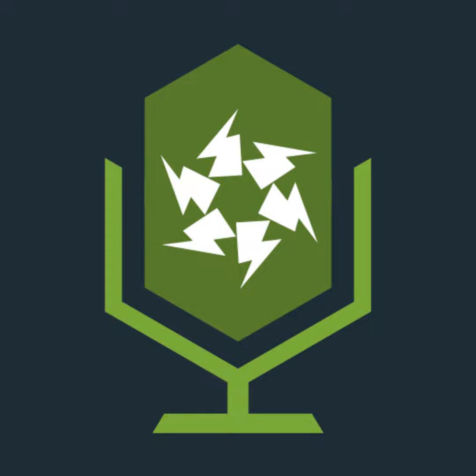Appendix 3 tells me 40 amp B requires 200 amp for instantaneous disconnection. Now I have to be careful how much I use that book though, because I need to understand the real fault current relative to the earth fault loop impedance. But for now, let's go with 200. So 200 amp will achieve disconnection. So 50 volts over 200.